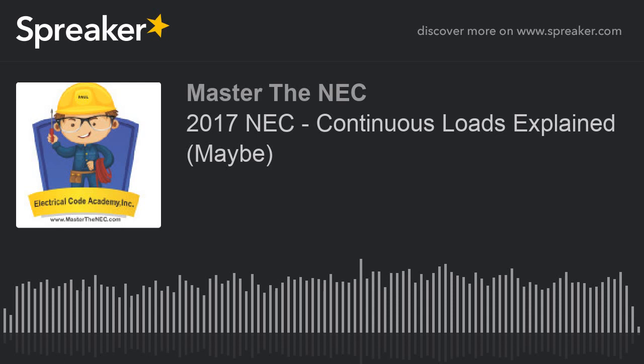Now, another thing to remember, if we weren't doing continuous loads, if I've got a 20 amp overcurrent device and I've got 20 amps worth of load, then I could run 20 amps non-continuously through that 20 amp device all the time. So what does that mean? I could have 20 amps of load, okay? You tracking with me? 20 amps of load running through that 20 amp overcurrent device for 2 hours, 59 minutes, and 59 seconds and still not be considered a continuous load, and I could run 20 amps through it. The moment that I run 3 hours or more continuously at its maximum current, then it becomes a continuous load.